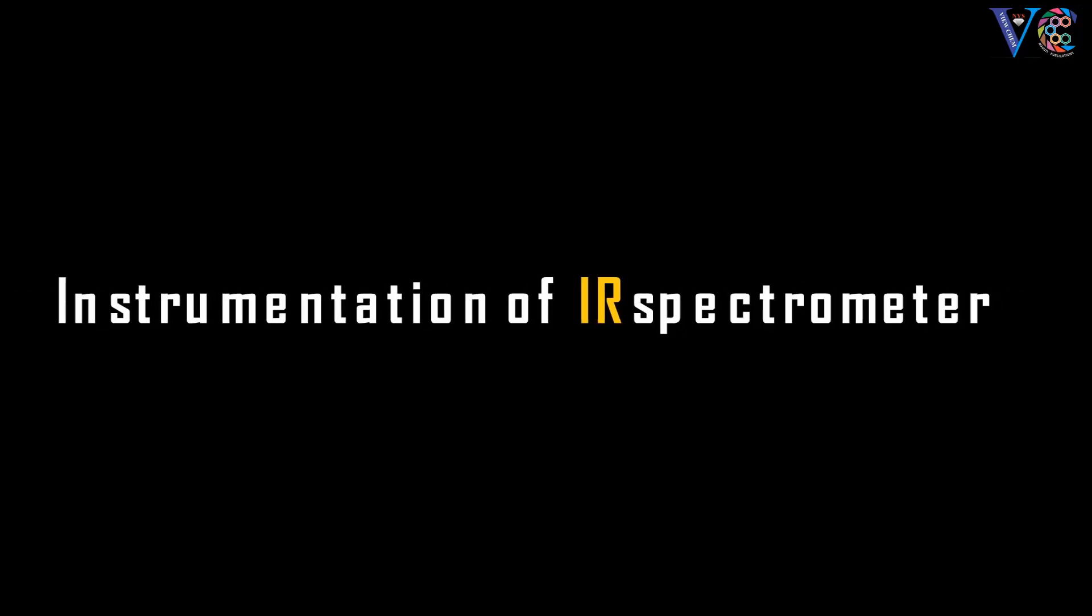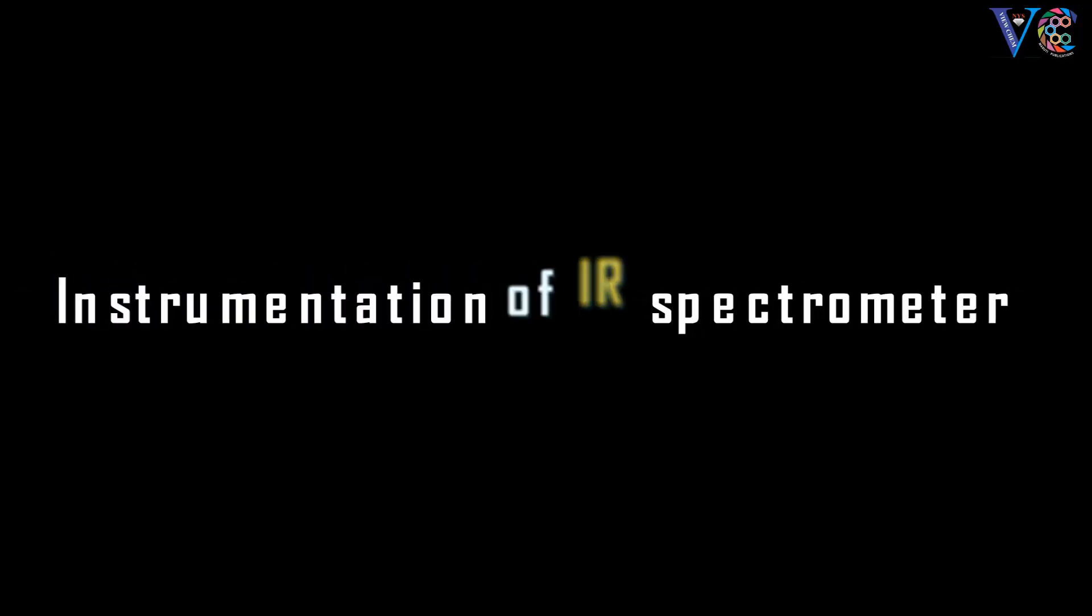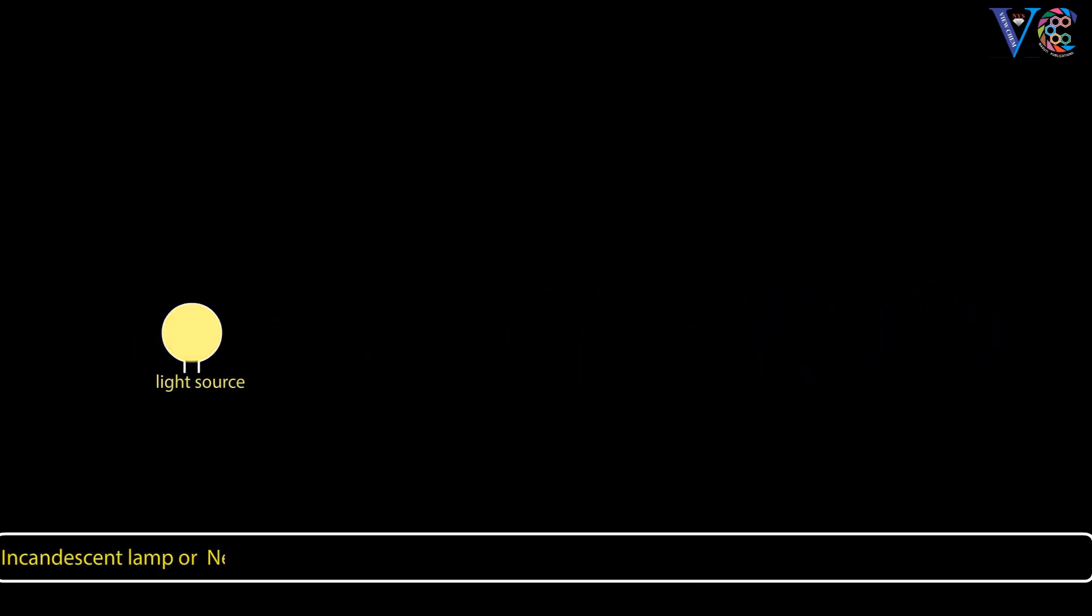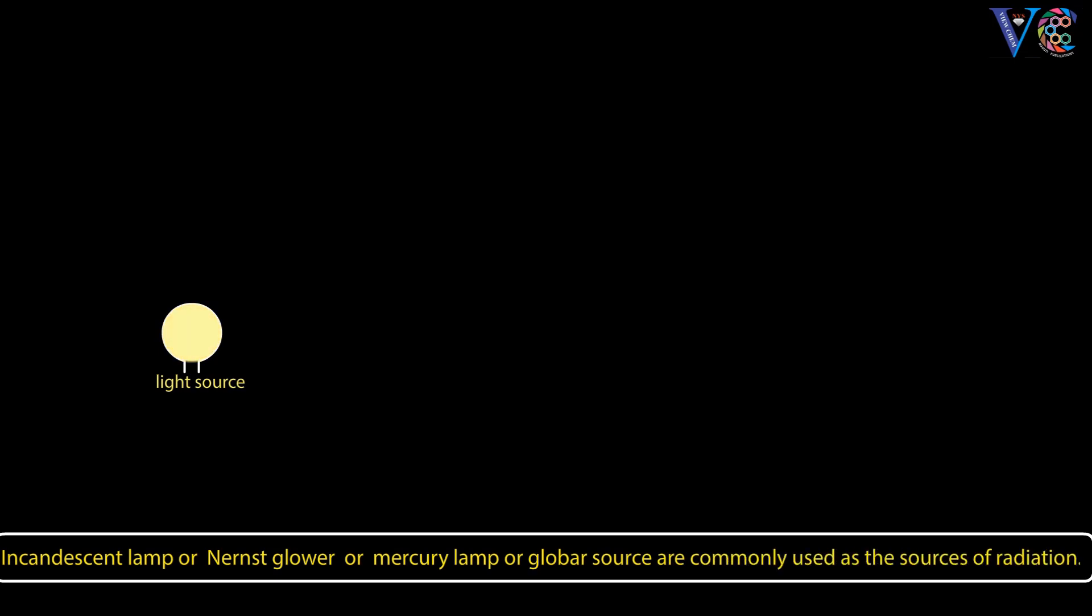Instrumentation of IR spectrometer. Incandescent lamp or Nernst glower or mercury lamp or globar source are commonly used as the sources of radiation.